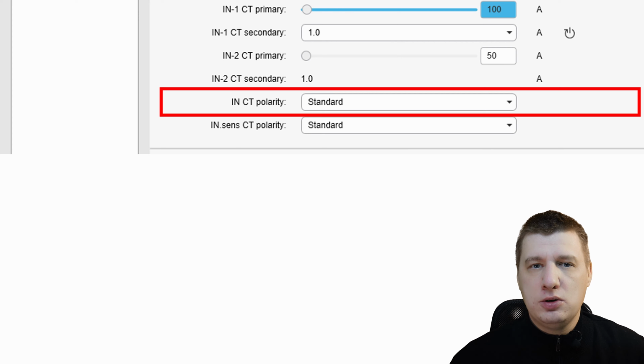If you have a network earthed through a small resistance, you might use sector mode instead of a simple half plane. This lets you define the specific tripping wedge, like 70 degrees, to make the protection even more selective. No direction mode turns off directionality entirely, making the stage behave like a standard non-directional overcurrent stage.